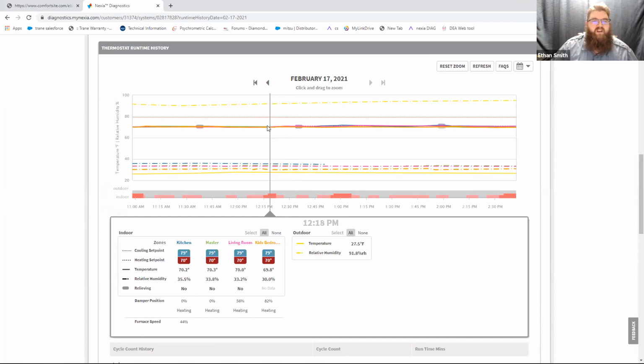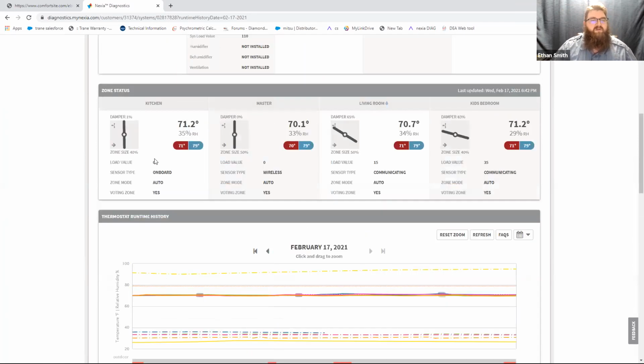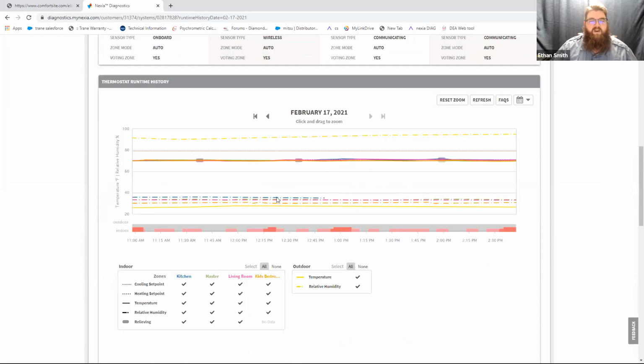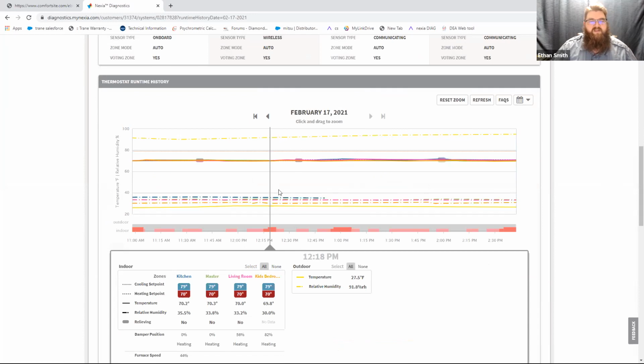Okay, and as we cycle in and out of these other zones calling, you'll notice that all those other zones, which were sized a little bigger, so the living room and the master are sized a little bigger, we don't have any air relief problems in those, because it's able to run the airflow on that furnace down enough that it doesn't have an excess air problem.